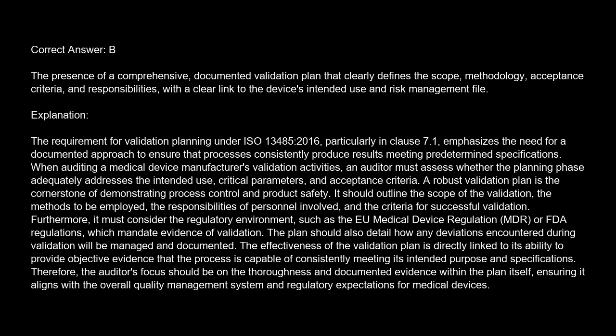The plan should also detail how any deviations encountered during validation will be managed and documented. The effectiveness of the validation plan is directly linked to its ability to provide objective evidence that the process is capable of consistently meeting its intended purpose and specifications. Therefore, the auditor's focus should be on the thoroughness and documented evidence within the plan itself, ensuring it aligns with the overall quality management system and regulatory expectations for medical devices.